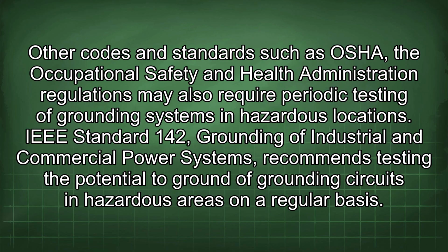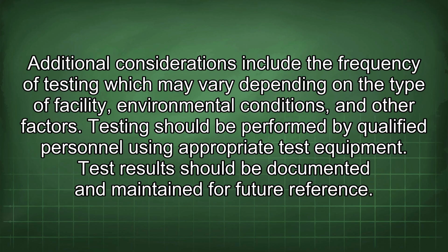IEEE Standard 142, Grounding of Industrial and Commercial Power Systems, recommends testing the potential to ground of grounding circuits in hazardous areas on a regular basis. Additional considerations include the frequency of testing, which may vary depending on the type of facility, environmental conditions, and other factors. Testing should be performed by qualified personnel using appropriate test equipment. Test results should be documented and maintained for future reference.